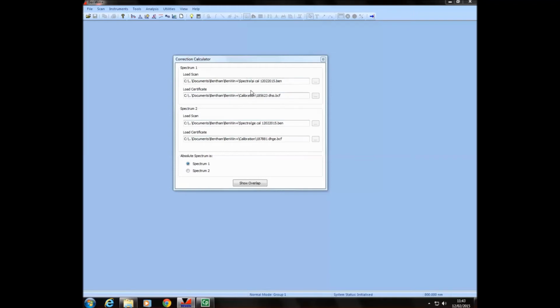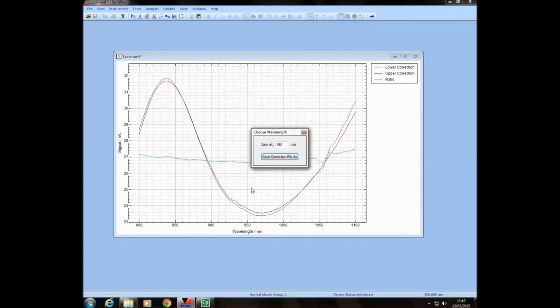The reason for that is that the silicon device is a 10 by 10 chip compared to the 5mm diameter germanium device. So it is more likely that the monochromatic probe would be fully measured by the silicon device than germanium device. And of course that depends on the size of the monochromatic probe used. In most cases there'll be very little difference. So the absolute spectrum is that of the silicon, and we show overlap.